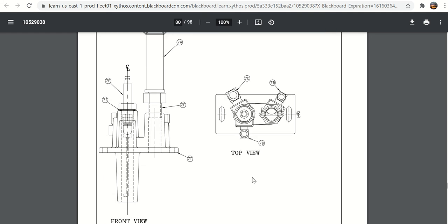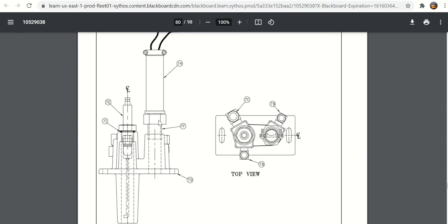Here's the pilot assembly here. This is the ultraviolet scanner. There's a stainless steel nut here, and you loosen that up. When you tighten this down, you never tighten these down with a crescent wrench. You just tighten them down to finger tight. There's a washer inside there, like a hose washer. You know, when you put a hose on a hose bib, you don't have to crank it down with a pair of channel locks to get it to seal. All you have to do is get it tight. You really don't need to get on this with a crescent wrench, because you'll crush that rubber washer, and you'll take the chance of breaking the glass that the ultraviolet scanner is enclosed in.